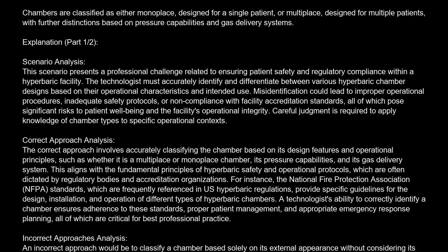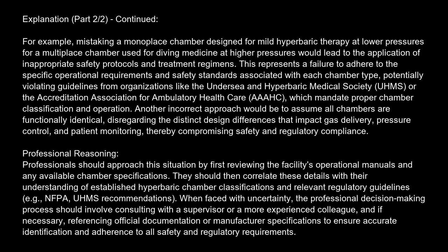Incorrect approach analysis. An incorrect approach would be to classify a chamber based solely on its external appearance, without considering its internal design, operational pressure limits, or intended patient capacity. For example, mistaking a monoplace chamber designed for mild hyperbaric therapy at lower pressures for a multiplace chamber used for diving medicine at higher pressures would lead to the application of inappropriate safety protocols and treatment regimens.